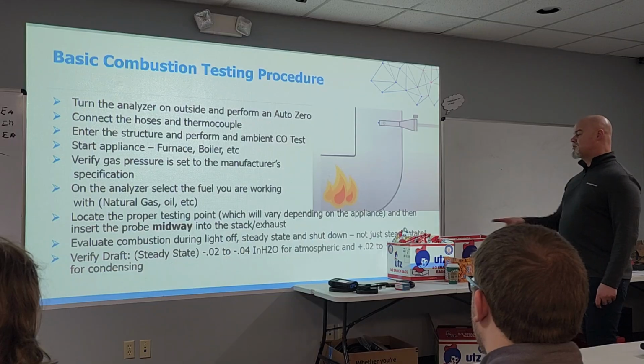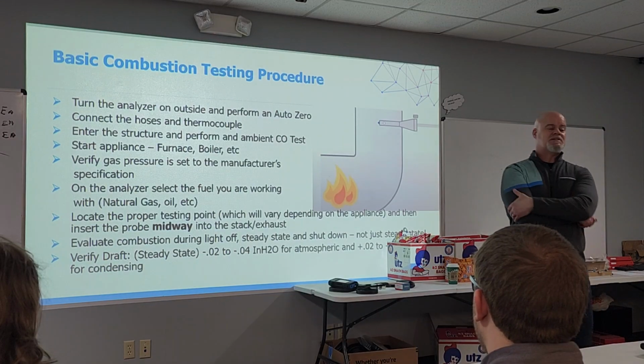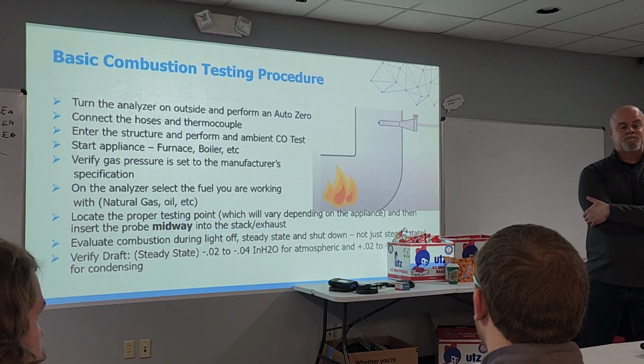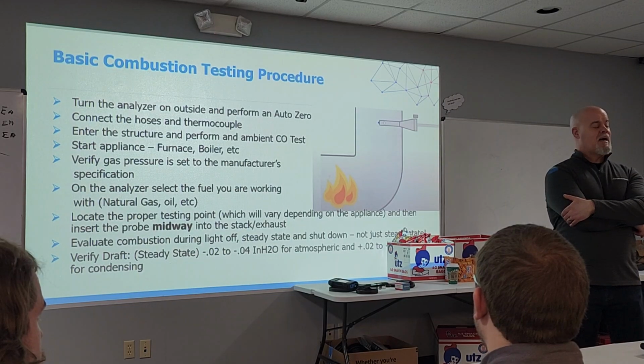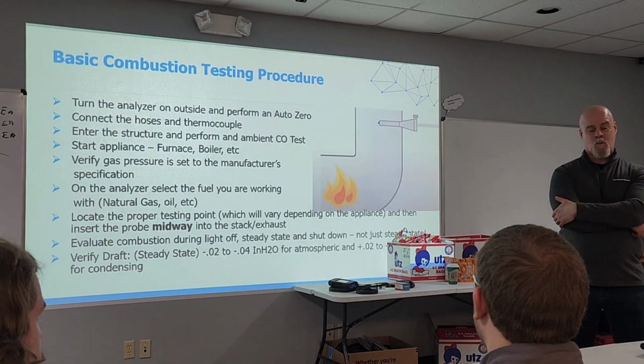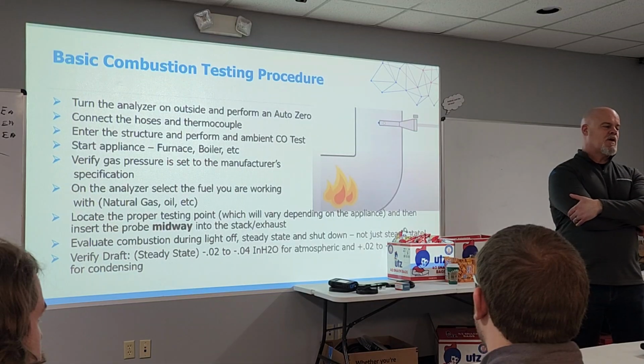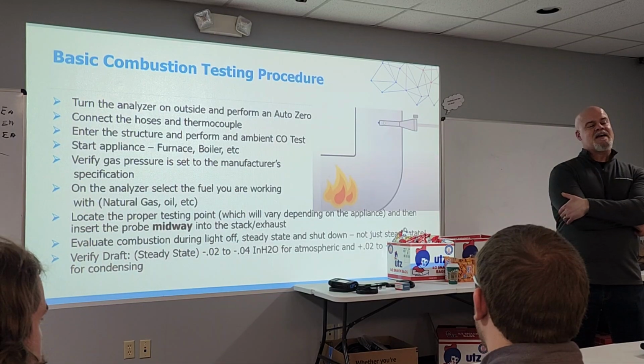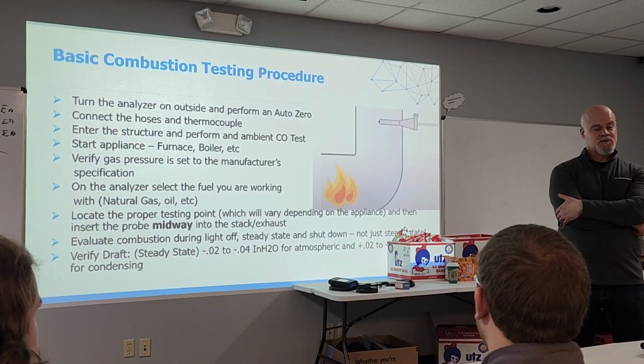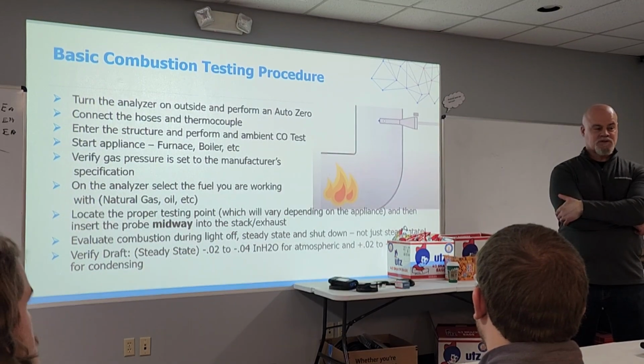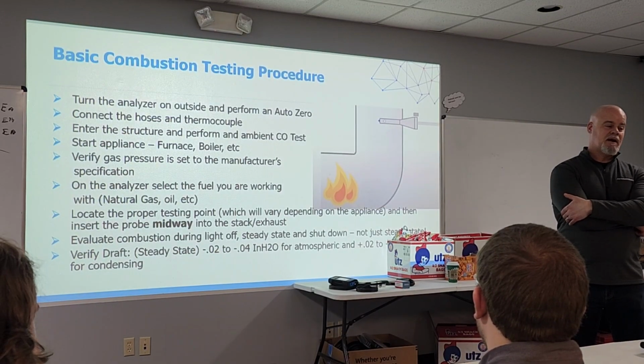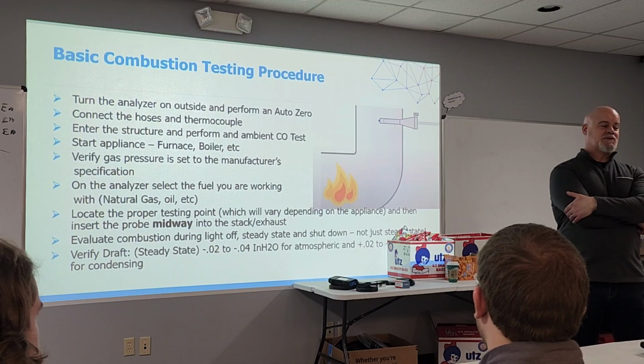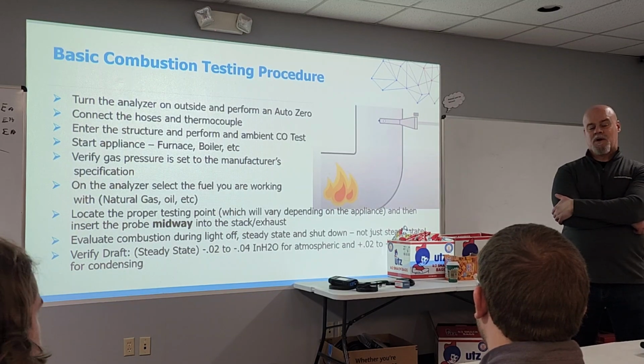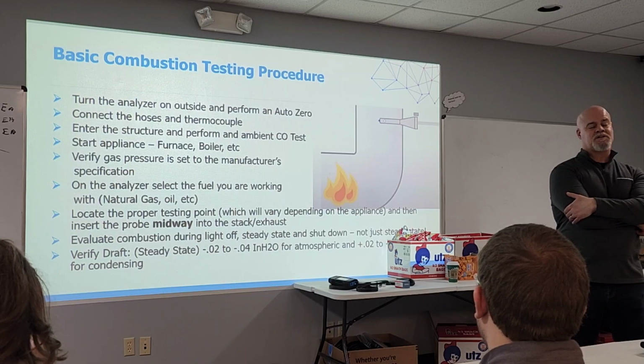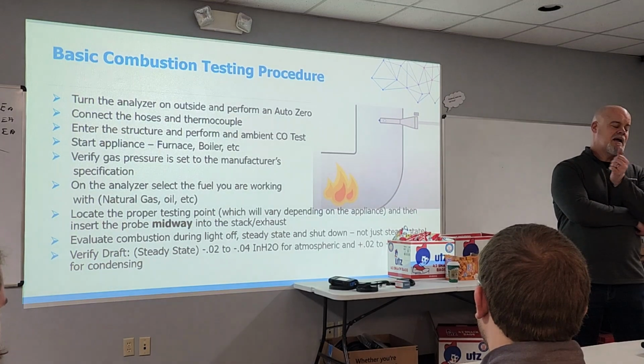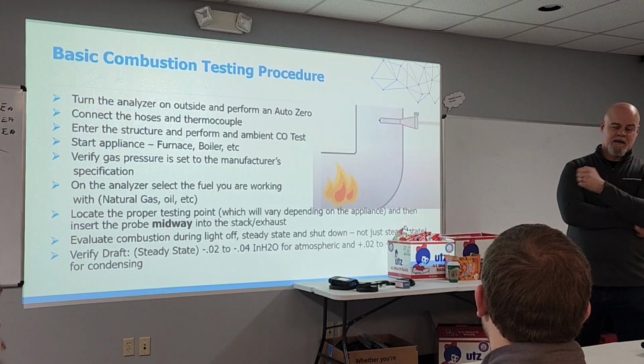And then we're gonna evaluate combustion during light-off. In the combustion world, when I say testing during light-off, that's like calling your mother a four-letter word. I'm not interested in being disrespectful to your mom. However, in the combustion world, that's what it is like. Why? Because we run the risk of overranging carbon monoxide sensors. If we test correctly and we use due diligence, you're not going to overrange your sensor if you're paying attention. If you have our analyzers at Sauermann, you're never going to overrange it because we give you programmable pump cutoff, which will actually cut the pump off before you even think about overranging that sensor, which means you pull the probe out of the stack, analyzer, take a breath for a second, put it back in and continue to test.